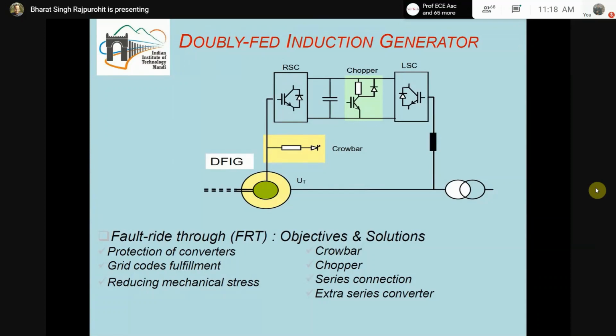And if the chopper is also not able to sustain the fault, then a signal goes to the crowbar for its operation. Once the crowbar operation is over, based on the grid voltage and frequency, the control set point is set for the doubly fed induction generator, so that once the crowbar comes out of the system, the generator will be able to remain connected and operate properly. So there is a control sequence for all these three operations.